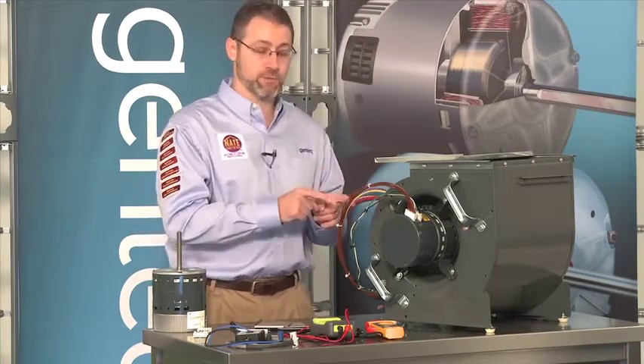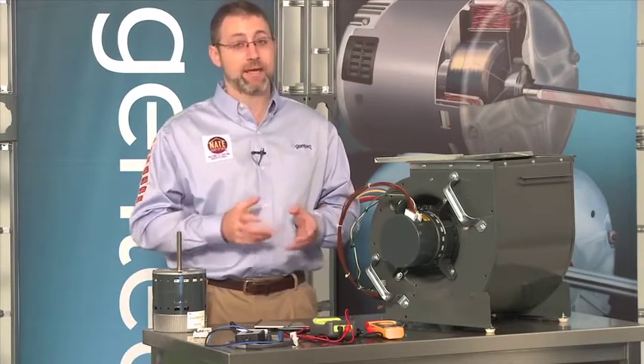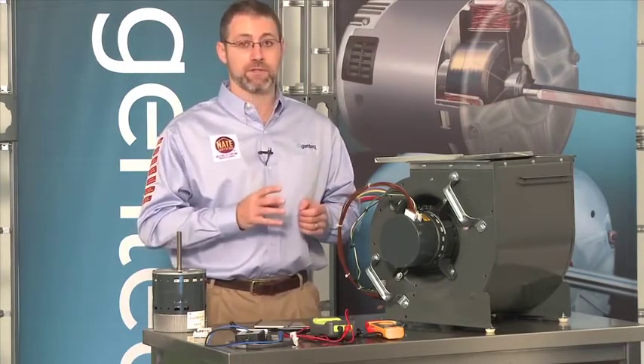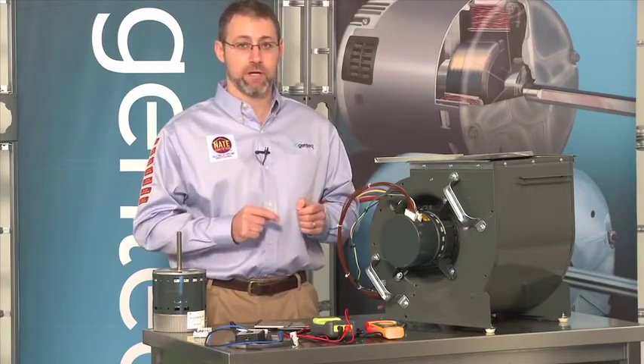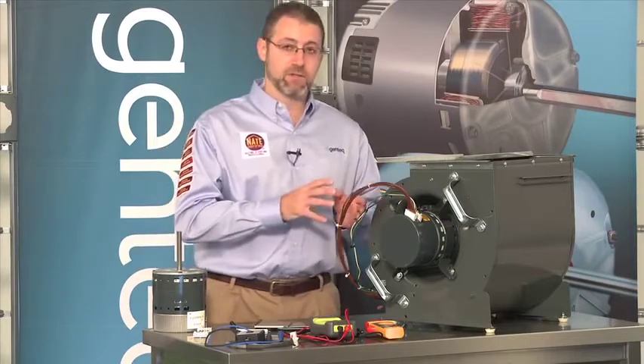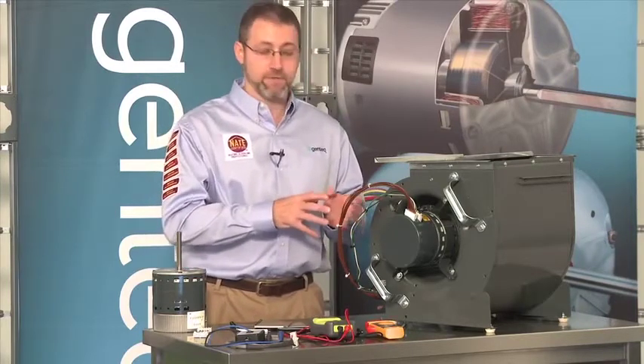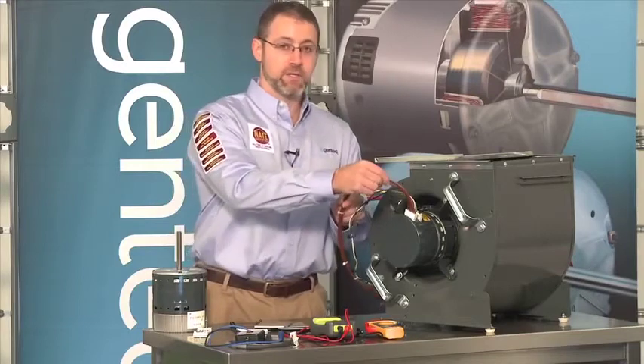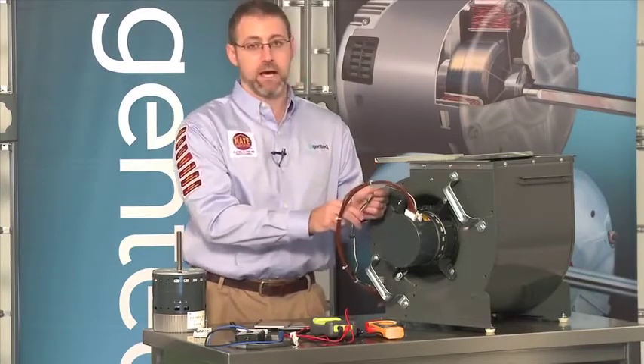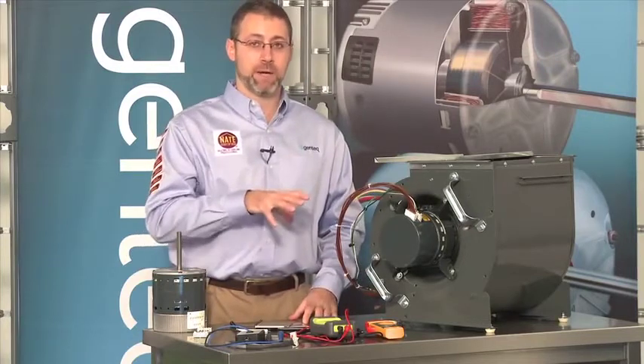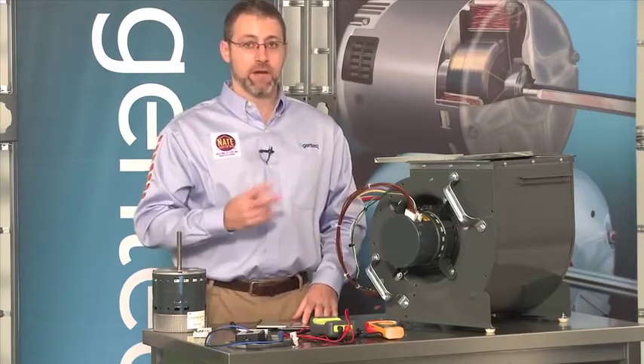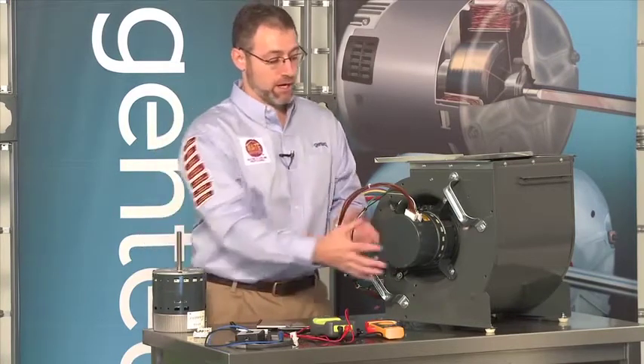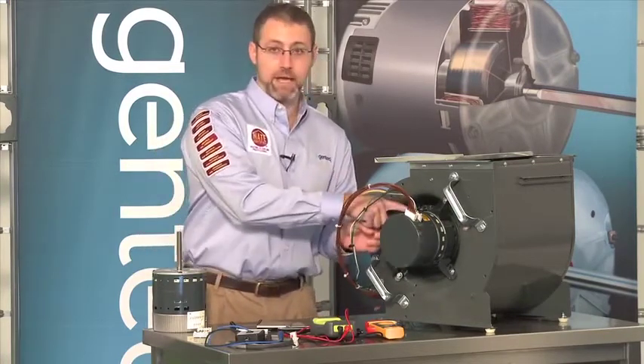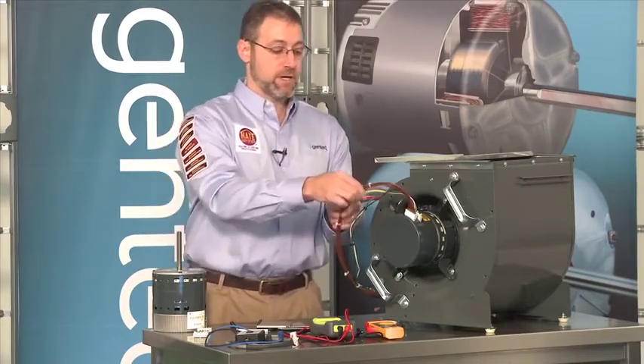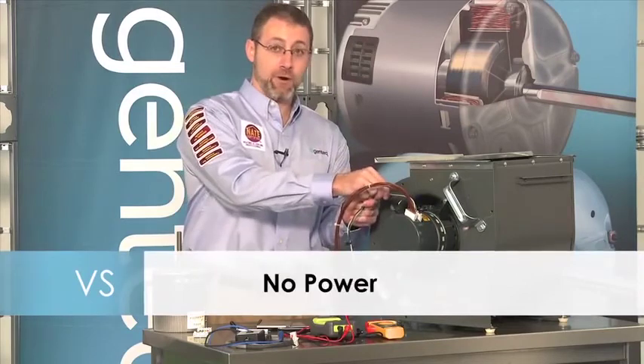So now let's talk about troubleshooting a motor that's not working. And that actually is very easy because there's only 4 things that can really be wrong with a variable speed motor that's not operating. Keeping in mind that this is an electronic device, and this electronic device needs 2 inputs to run. It needs the communication input to tell it when to turn on, and it needs the high voltage input to give it the power to operate everything inside the motor. The other 2 potential things that could be wrong with the motor are a bad control or a bad motor itself. So again, the 4 things: no communication to tell it when to turn on, no power to run, a bad control, or a bad motor.